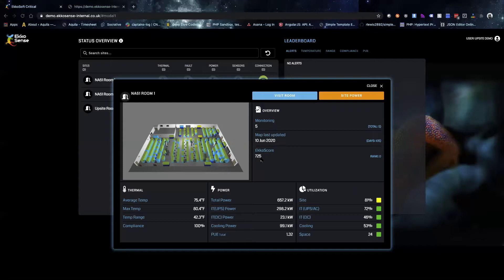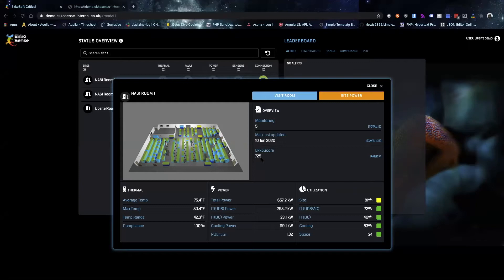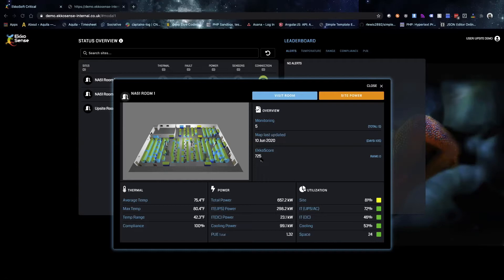The stability of those intake temperatures and how much they're fluctuating, which is an important indicator of efficiency, and also the utilization of the installed cooling capacity. That's a metric that is very often overlooked and the utilization of cooling infrastructure is generally quite poor. This combined EkkoScore is a very useful tool for understanding where your facility sits in the potential for improvement.